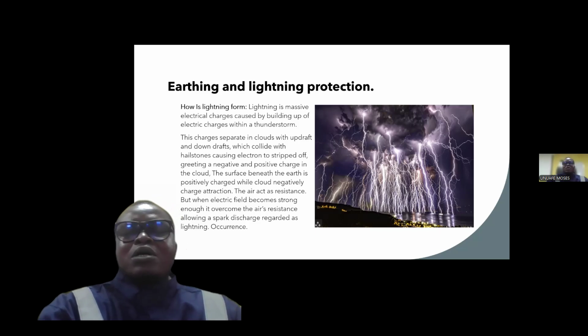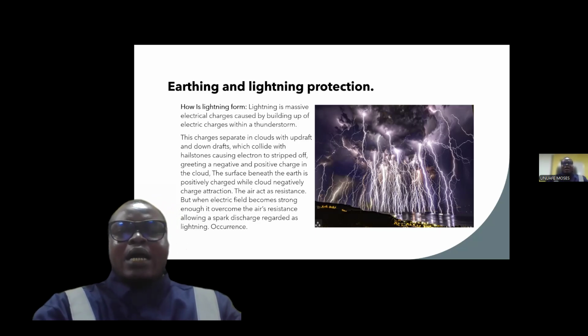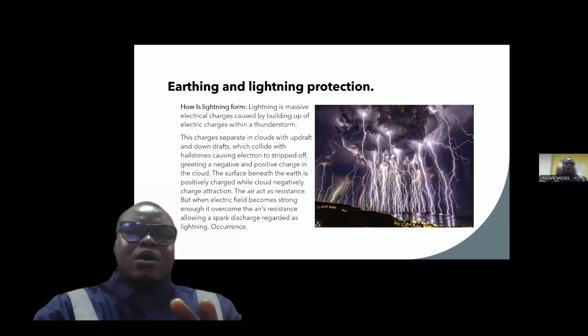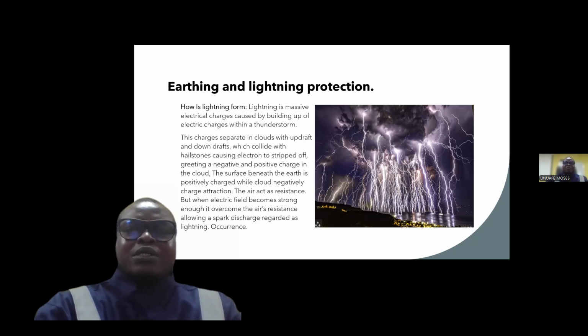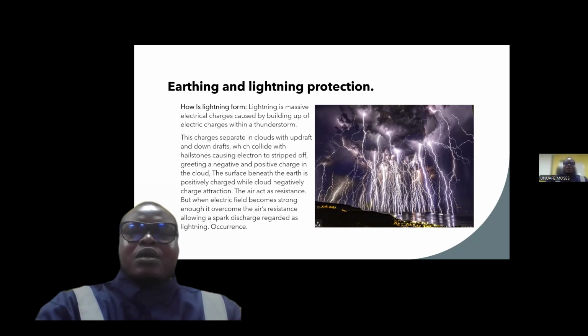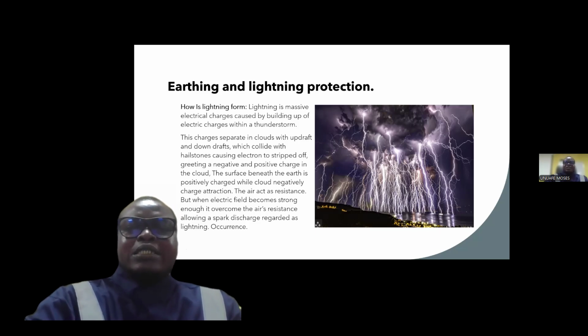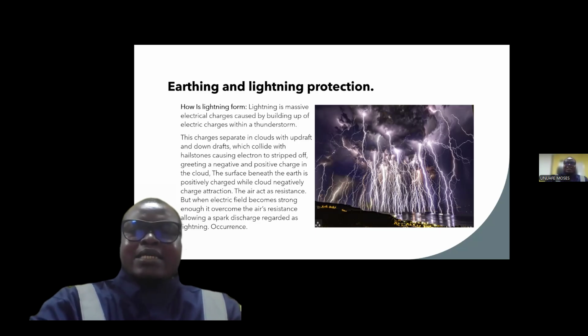Let's take a scenario that relates to an operational environment like manufacturing sites. For instance, a product tank with an overfill protection device installed on top, projecting above the tank rooftop. During a thunderstorm, lightning hits 50 meters away. The electromagnetic pulse induces a voltage on the overfill device, resulting in short circuit of the primary sensor microboard.